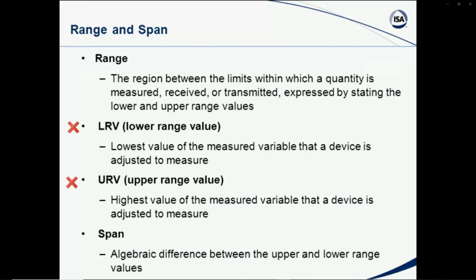Then the range, we'll talk about the calibrated range many times, and when we say the calibrated range, that's the region between the limits within which a quantity is measured, received, or transmitted, expressed by stating the lower and upper range values. For instance, the calibrated range for that first transmitter, 0 to 100 psig. In the case of the temperature transmitter, it would be 50 to 250 degrees F, or Fahrenheit. So that would be the range.